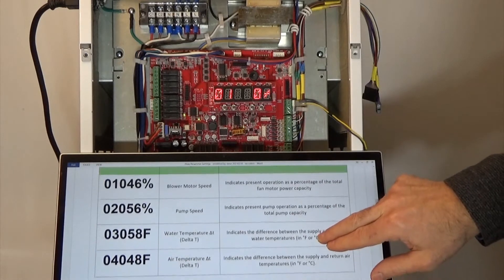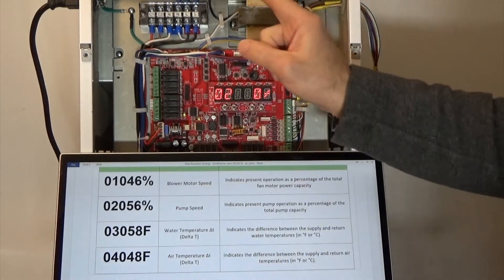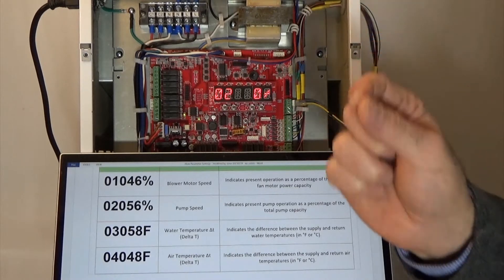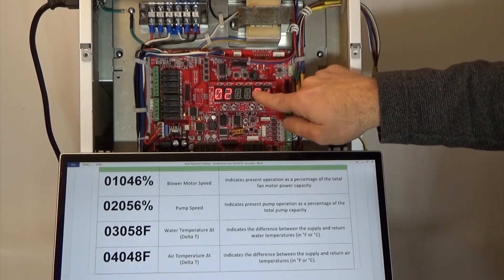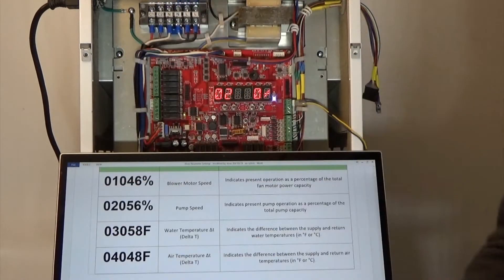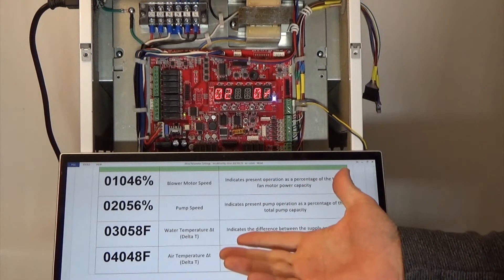Parameter number two — let's use the up button to go there. Parameter number two is the pump speed. On the iFlow we have variable speed pump control built into our unit. This will tell us what the actual pump speed is based on the output we're supplying to it, as a percentage of total power. When we're supplying 100% power to the pump, that would be 100% capacity. As we supply a lower percentage, you would see a lower pump speed and a lower flow rate through the unit.